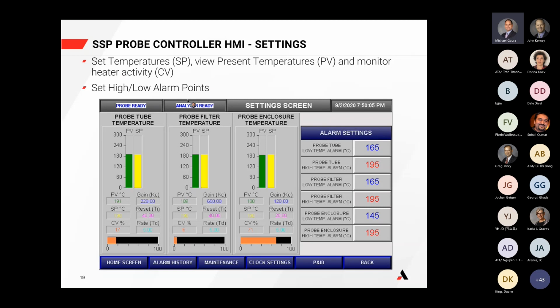One other item to note here, and again we've seen this on a couple of screens and I didn't mention it, is that as you scroll through these different display screens, you will see that we consistently remind the user what the status of the probe assembly, this is a severe service probe, as well as the analyzer are, just so it really jumps out at users. If there's something going wrong with one of the components, they'll be notified as quickly as possible while they're standing there in front of the user interface.